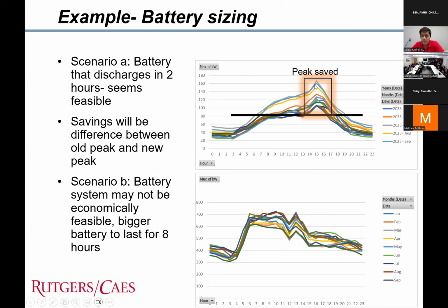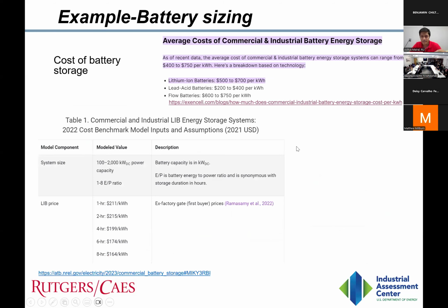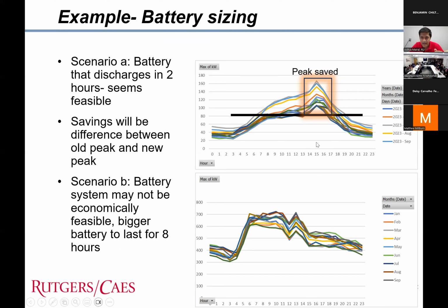Because of the way peak demand works, when I reduce one peak, the facility will be charged for the next peak that comes up. It's not that I'm going from 160 to zero. I can go from 160 all the way down to zero, but then they still have a peak sometime around 11 a.m. or 10 to 12, at around 80. So the facility is not going to be charged $0 for demand, but they're going to be charged for that second peak. So peak shaving is mainly the difference between the maximum peak and the next maximum peak that we see.